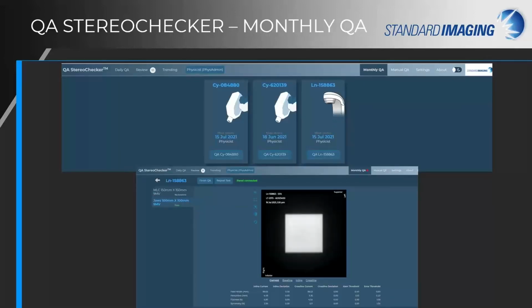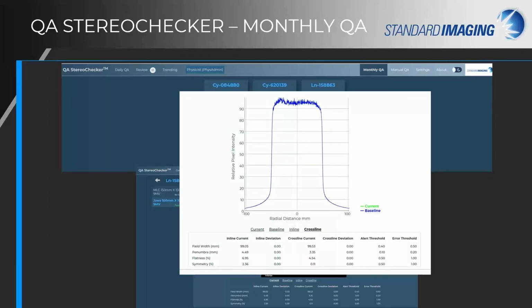Single field analysis for Linac and CyberKnife QA is reimagined as monthly QA. Like all daily QA tests, single field images are acquired, analyzed, results displayed, saved, and trended with a single click on the Start button. Metrics for flatness, symmetry, field width, and penumbra are calculated and trended. Full inline and crossline profiles are provided.